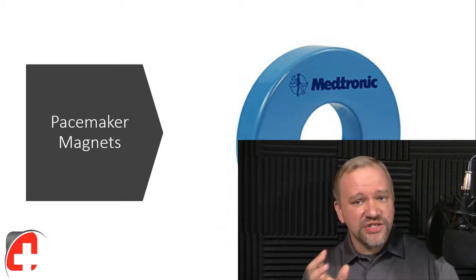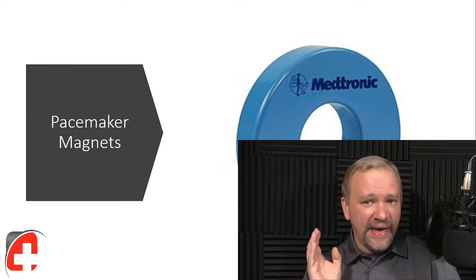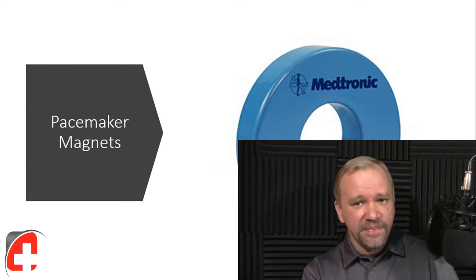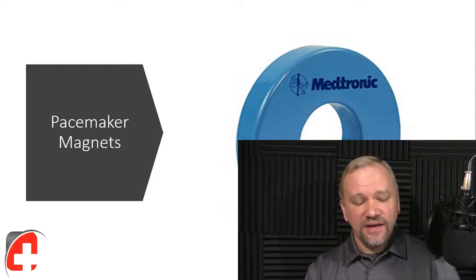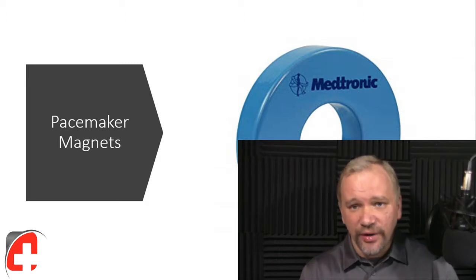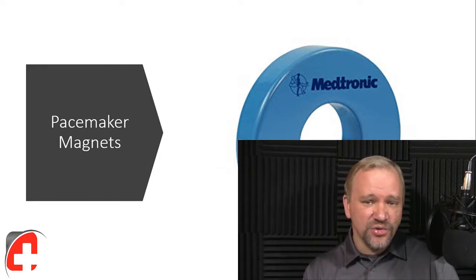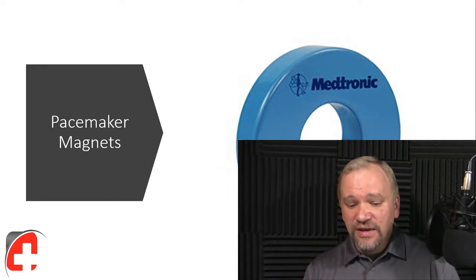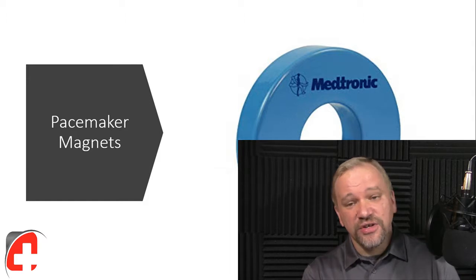A pacemaker magnet shuts off a lot of the features of the pacemaker. It changes it from whatever its native programmed rate is. It sets it back to being a VOO pacemaker. It'll just pace the ventricles, and it won't sense, it won't time anything, it won't trigger anything. It will just pace the ventricles at a set continuous rate. And this is useful for things like diagnostics. They can actually figure out the battery, because when it goes to that set rate, if there is a dip in voltage, the timing between the spikes will actually increase a little bit, and so will some other features like amplitude. So they can actually look and see what the patient's pacemaker battery status is by using a pacemaker magnet.